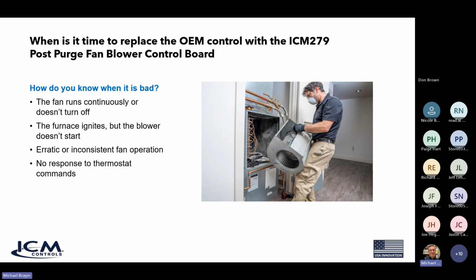So since this is a replacement to an OEM product, it's great to talk about when it is time to replace the OEM control. How do we know when our board needs to be replaced? First, the fan is running erratically. It runs continuously or doesn't shut off regardless of the signal coming from the thermostat. Maybe the furnace ignites, but the blower doesn't come on. So the furnace is generating heat, but the heat can't be distributed throughout the house. It just has erratic or inconsistent fan operation, starts and stops erratically in the heating or cooling cycle, or there's just plain no response to the commands from the thermostat. Those are some of the key times when you'd want to consider, hey, maybe the fan blower control board needs to be replaced.